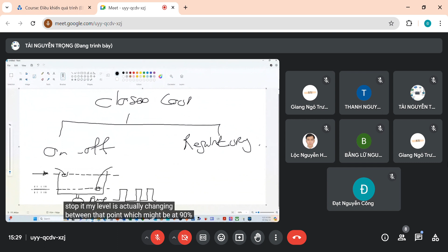As the level gets high, I start the pump, and the level drops down until I get to that low point, then the pump stops and the level starts to rise. When I run the pump the level drops down, then rises, then drops down again. These are two digital signals that I feed into my PLC. Kabu, does that explain it? So my PLC can work with on-off signals.